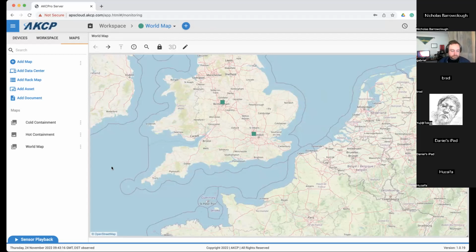The heat map changes instantaneously all the time, immediately reporting any problems. The CFD simulations, depending on the power of the computer, could take an hour to run to show you an airflow, and then you could rerun it once an hour, once every 2 hours, depending on how many computers you assign to it. But I wasn't sure that everybody understood that there was a difference between the technology that Nick was showing and the technology that Gabriel is showing. They're both useful, but there are some differences. Sorry for the interruption again.